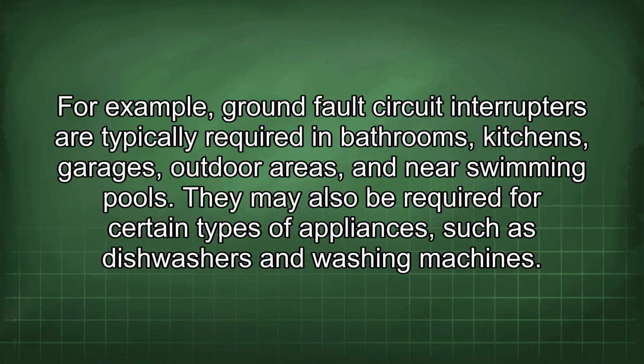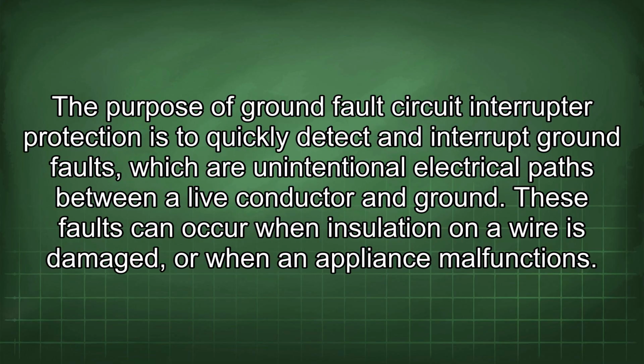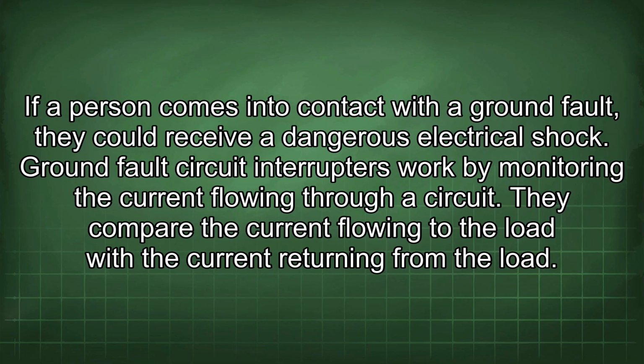For example, ground fault circuit interrupters are typically required in bathrooms, kitchens, garages, outdoor areas, and near swimming pools. They may also be required for certain types of appliances, such as dishwashers and washing machines. The purpose of ground fault circuit interrupter protection is to quickly detect and interrupt ground faults, which are unintentional electrical paths between a live conductor and ground. These faults can occur when insulation on a wire is damaged or when an appliance malfunctions. If a person comes into contact with a ground fault, they could receive a dangerous electrical shock.